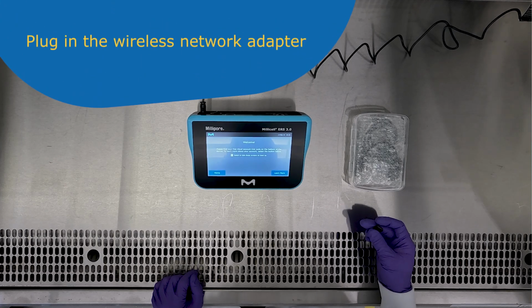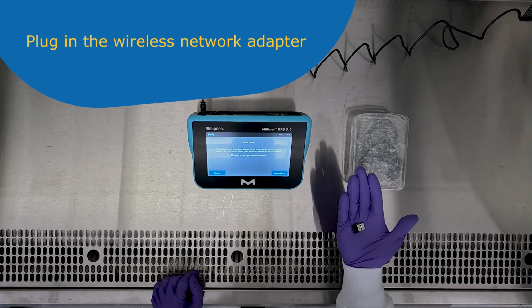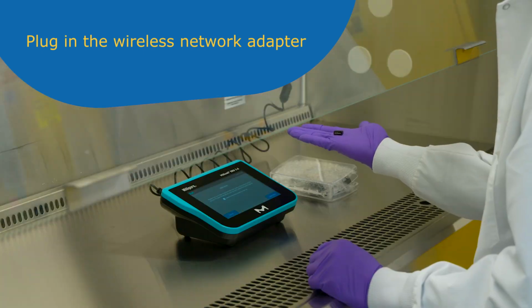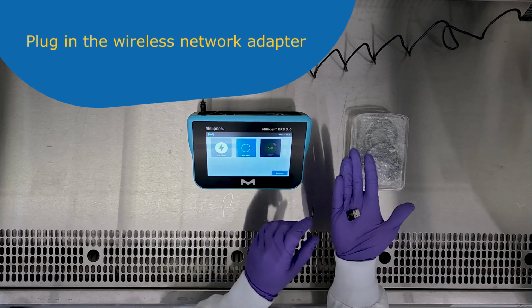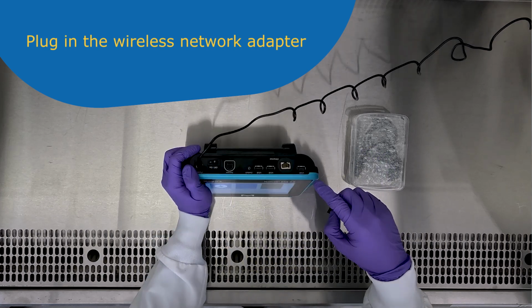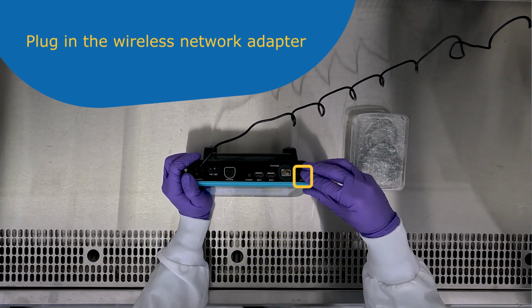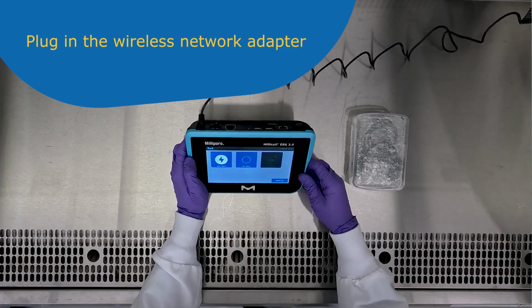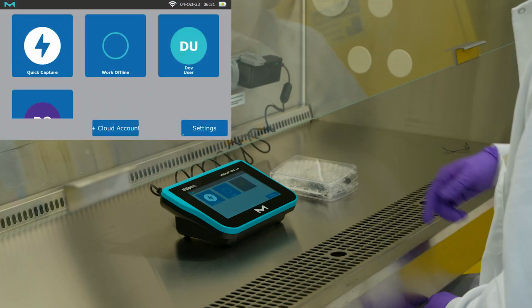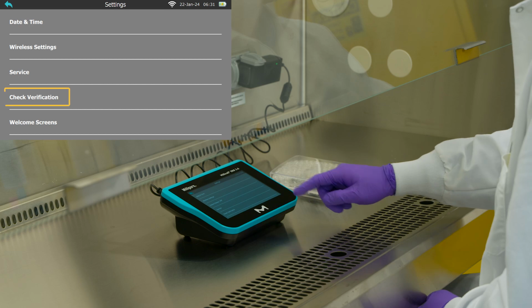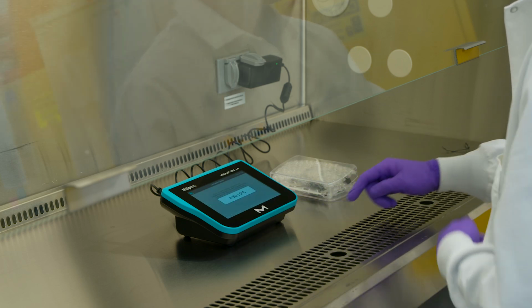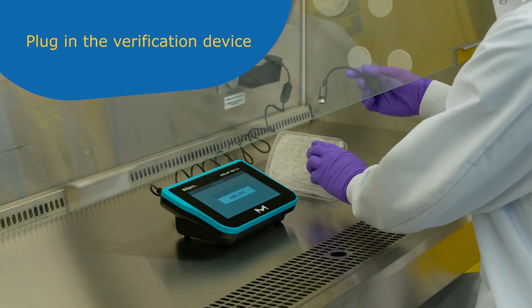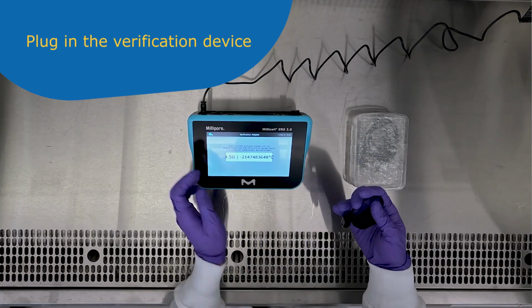Plug the wireless network adapter into the USB port on the back panel of the instrument. Then go to Settings on the touchscreen and click on Check Verification. Once complete, plug the verification device into the port labeled Sensor.